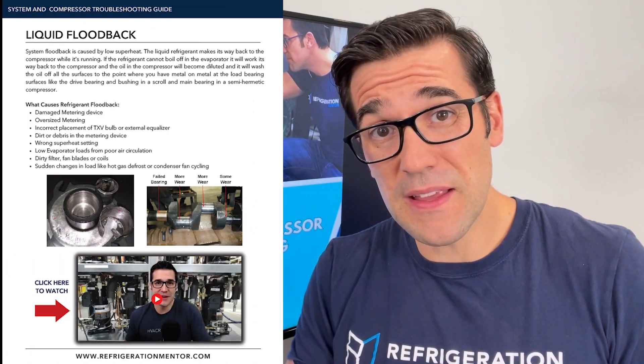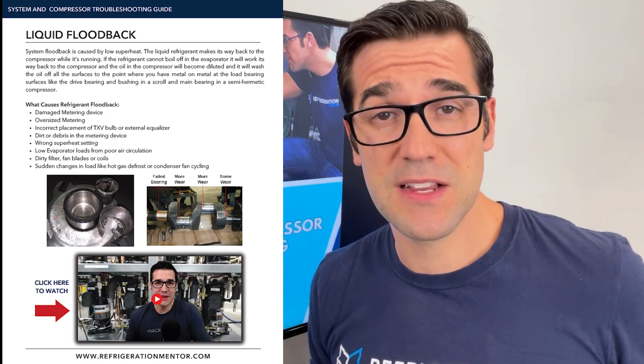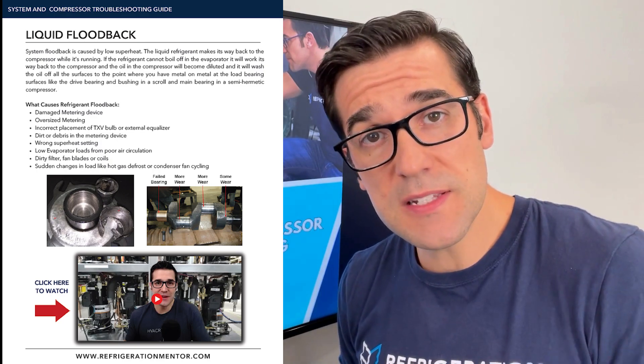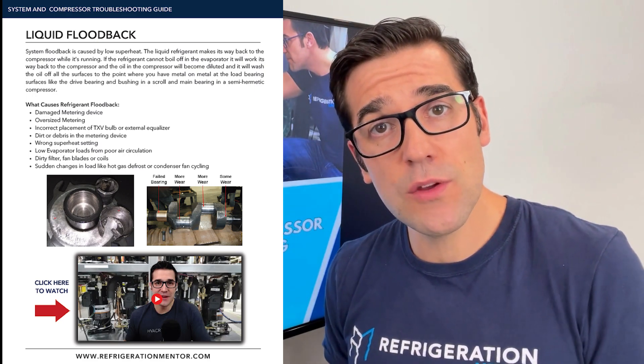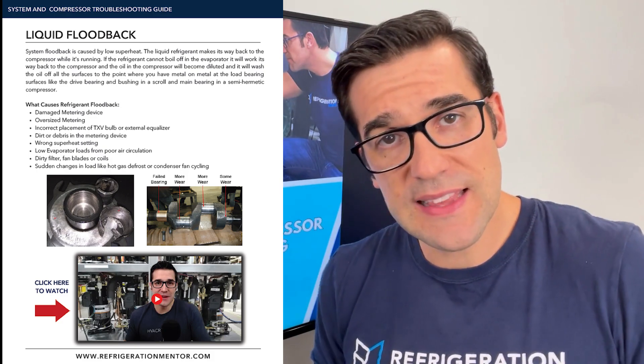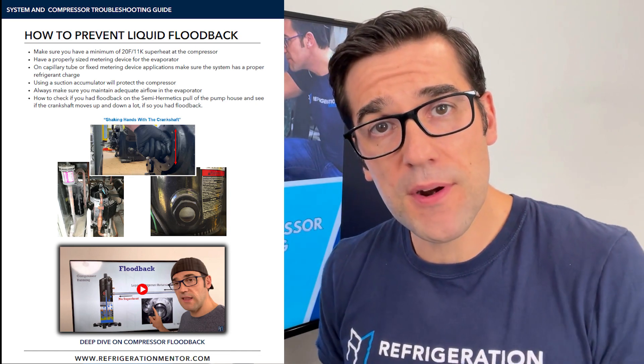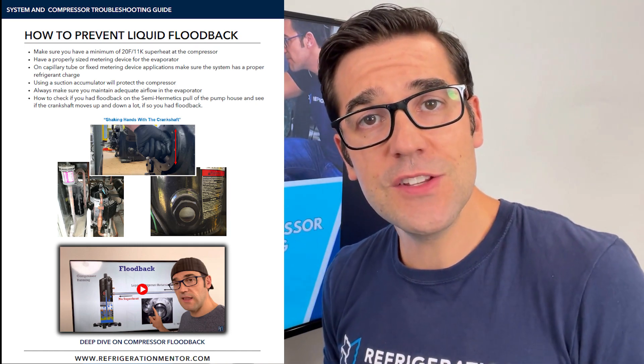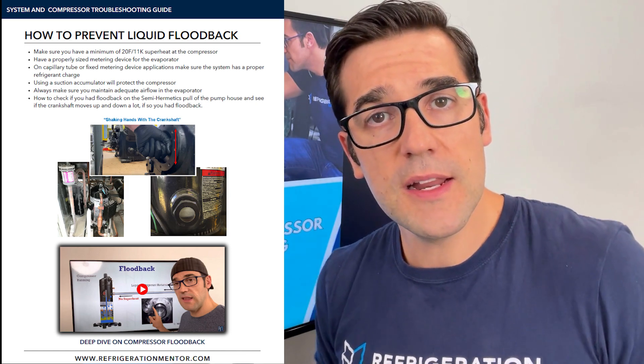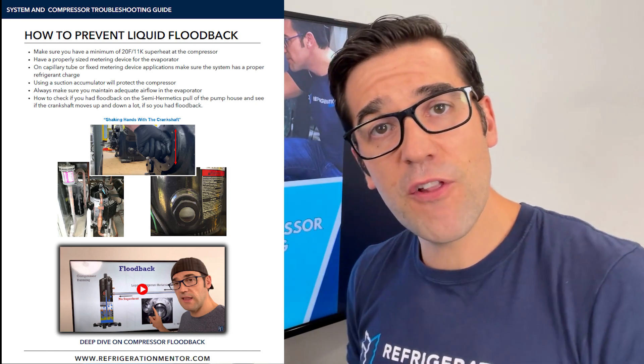Or there's floodback. Mr. Service Manager, I understand when a compressor fails from floodback by looking inside — I know the checks to do. Floodback is caused any time the compressor is running and refrigerant returns back to the compressor. When that happens, it starts to displace the oil, it starts losing lubrication, and because of that the parts inside the compressor start to wear. I understand the wear patterns that happen inside there, which lead to that failure. So when I install the next compressor, I know to check the metering device to see if it's properly functioning, make sure all the evaporator fans are running, make sure the evaporator is not plugged, and make sure airflow is proper — these are some of the things that cause floodback.